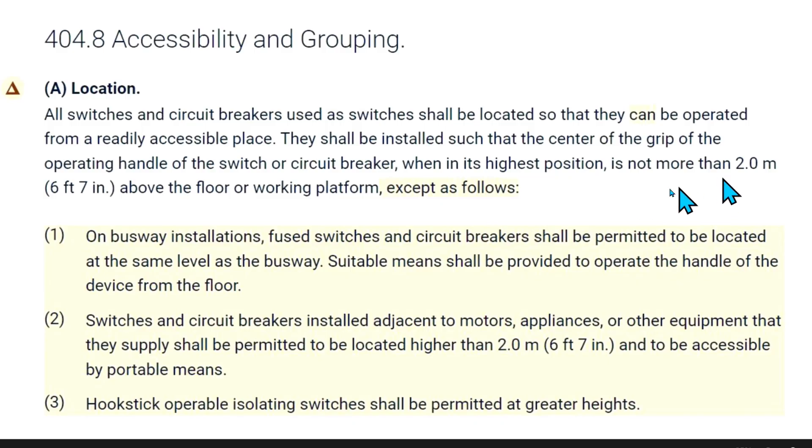And remember, our topmost circuit breaker was at 1.98 meters, 6 feet 6 inches above the floor. So the center of the grip of the operating handle of the switch or circuit breaker when in highest position is not more than 2 meters, 6 foot 7 inches above the floor or working platform, except as follows.